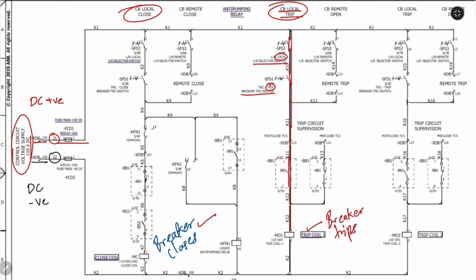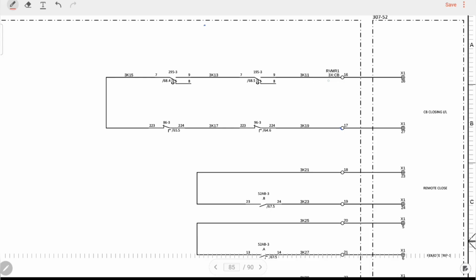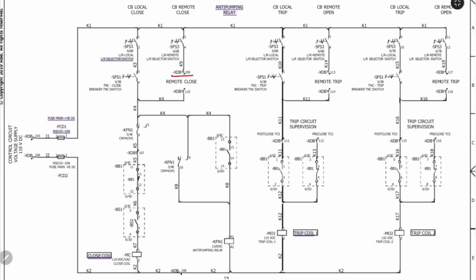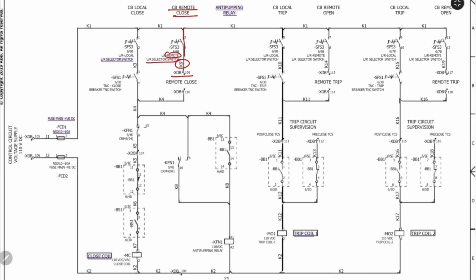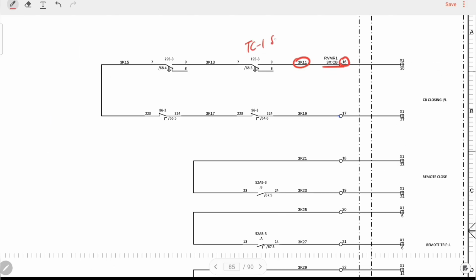Now let's connect the breaker to the Siemens protection panel for remote control. Connect Siemens terminal 3XCB16, 3K11 to breaker terminal XDB109, K9. This provides the remote close permission path whenever the local remote switch is in the remote position. Internally, the Siemens panel verifies that both trip circuit supervision relays are healthy and that master trip relays 86 and 96 are reset.